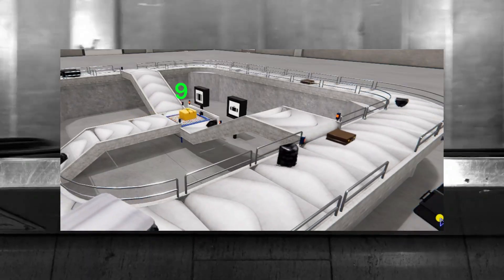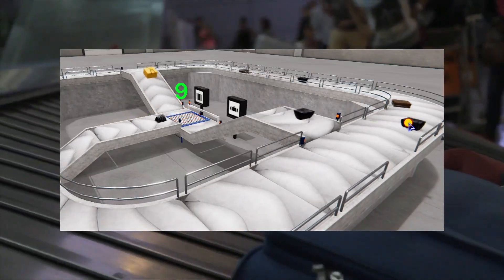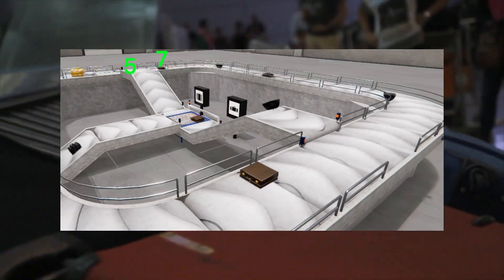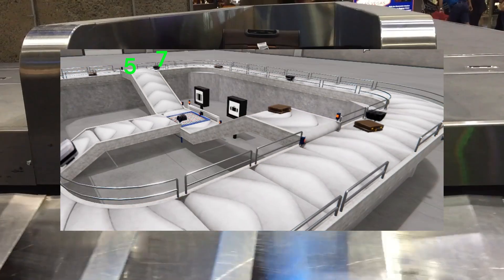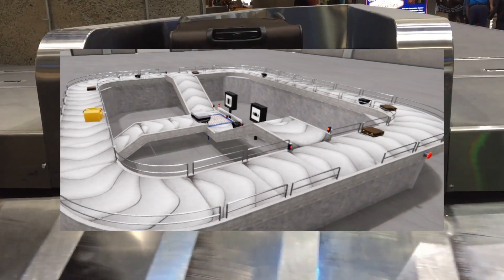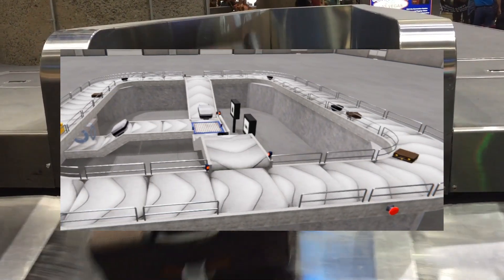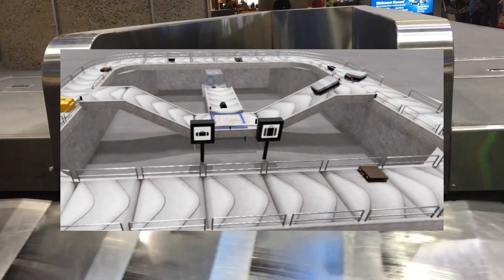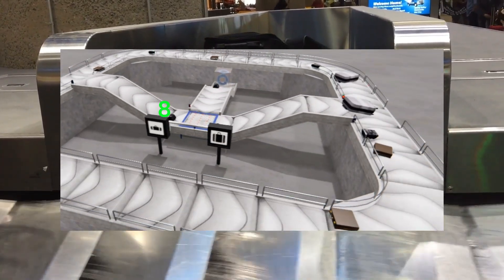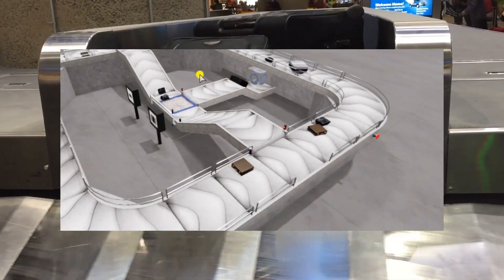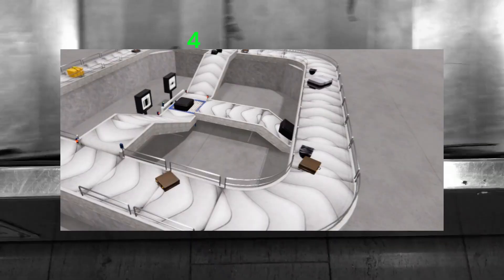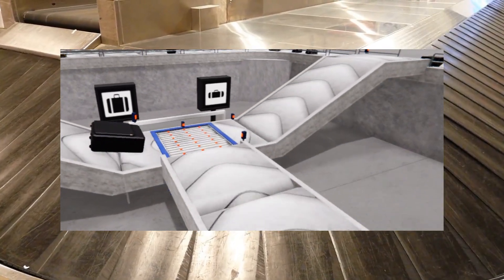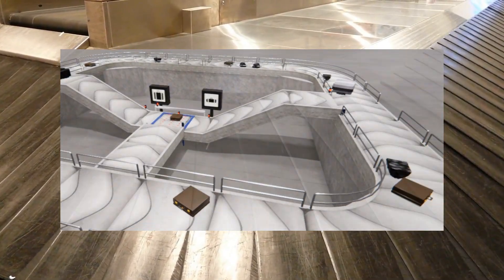When photo 9 sees the bag, the left conveyor turns on, sending it up until it sees photo 5. If photo 7 or a time delay is not on, then the bag will enter the top main conveyor. This is a small bag if photos 3 and not 1 are on. The distribution run to the right will turn on, sending the bag to the right. When photo 8 sees the bag, the right conveyor turns on, sending it up until it sees photo 4. If photo 6 or a time delay is not on, then the bag will enter the top main conveyor.